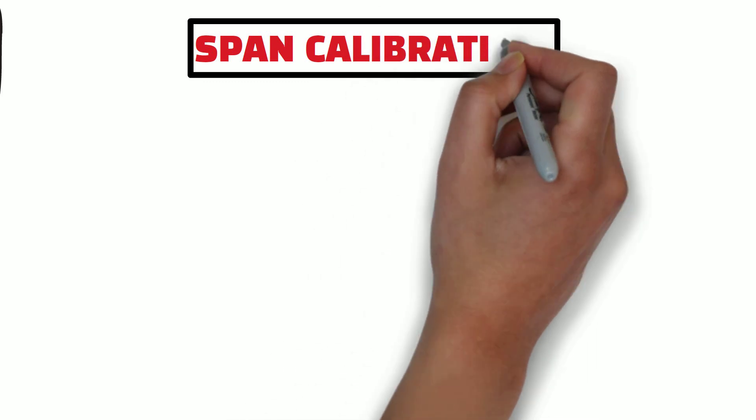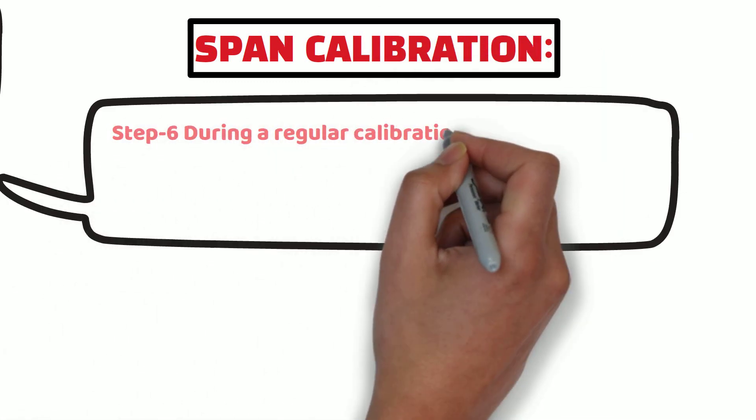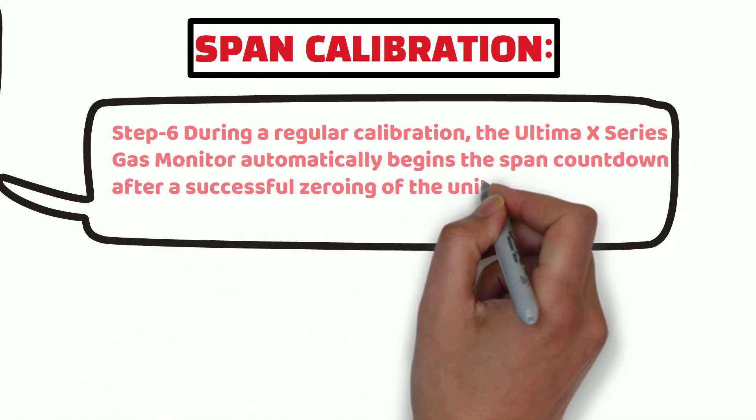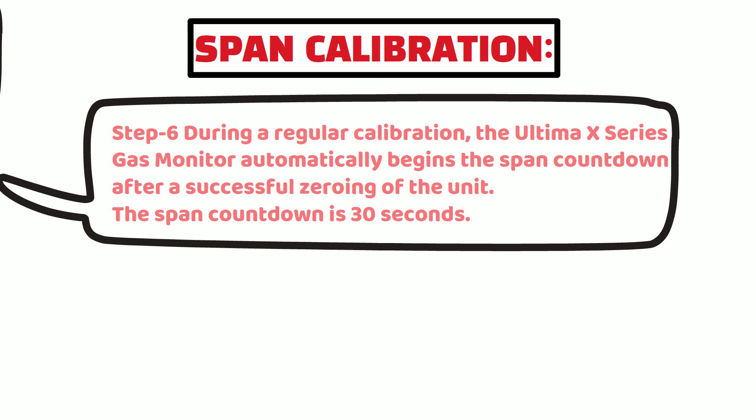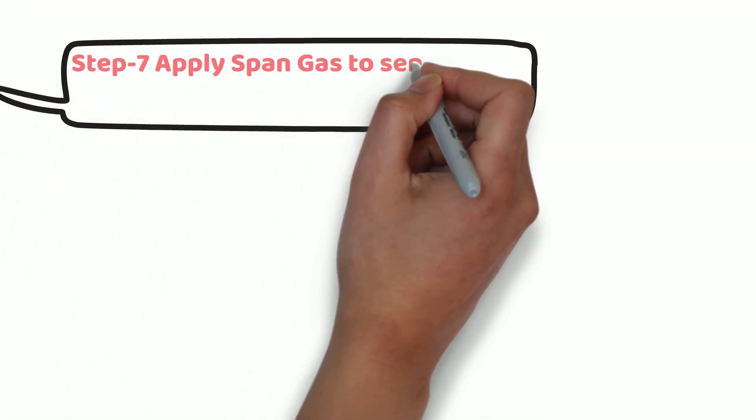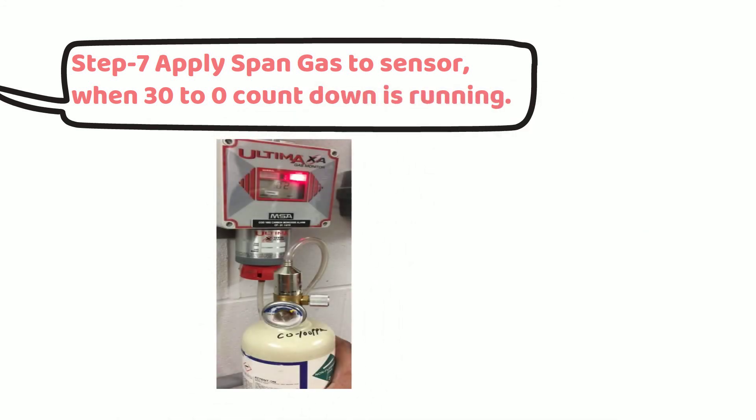If the zero calibration is successful, gas monitor automatically begins the span countdown. Span countdown is 30 seconds. Now apply span gas to sensor when 30 to zero countdown is running. Make sure that you apply correct concentration gas to sensor.